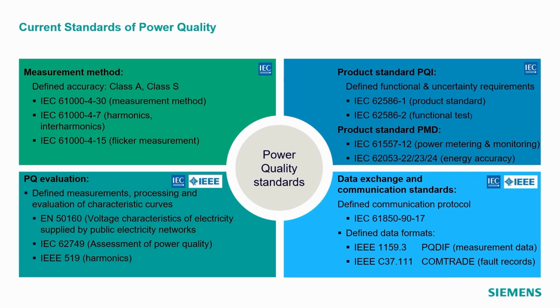Block 2 shows the product standard for the so-called power quality instruments, PQIs. There are 2 different classes of the PQIs defined, class A and class S. And for each class, the functional and uncertainty requirements are described in these 2 product standards. Part 1 is the product standard itself, and part 2 are the functional tests which have to be passed by power quality instruments, class S or class A.